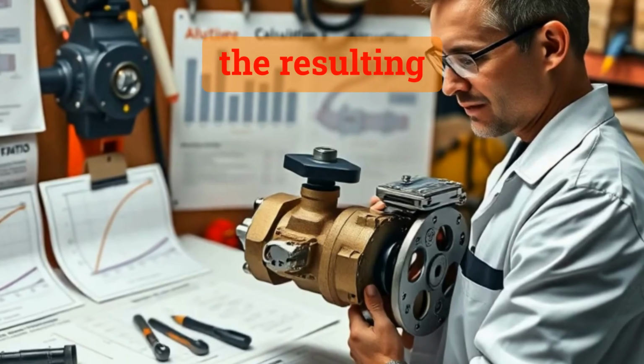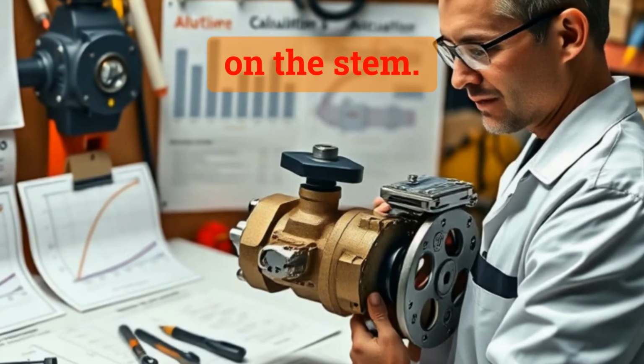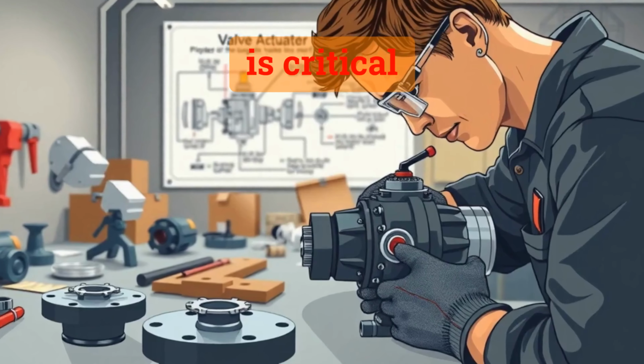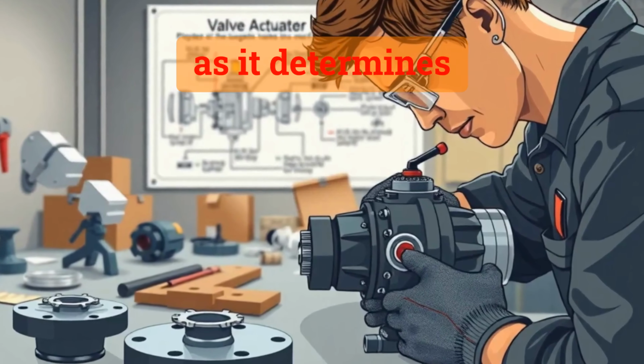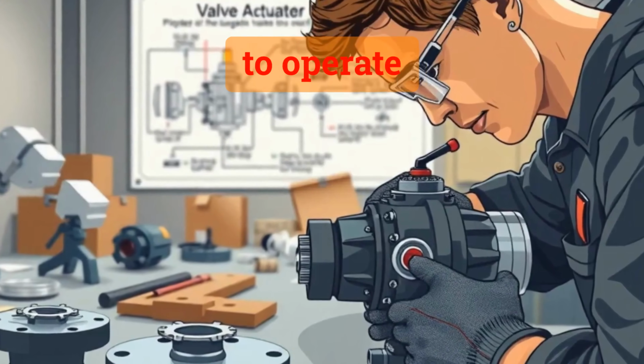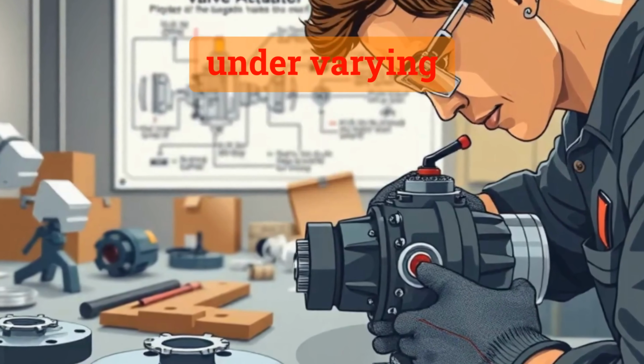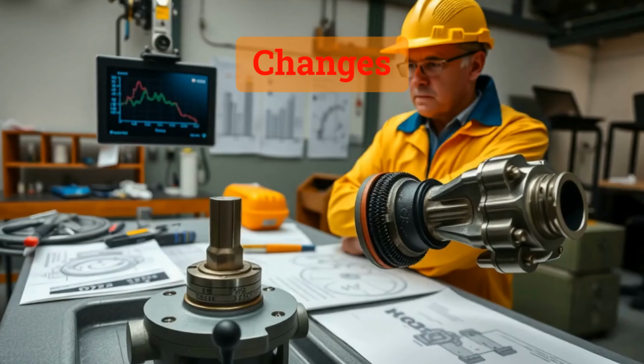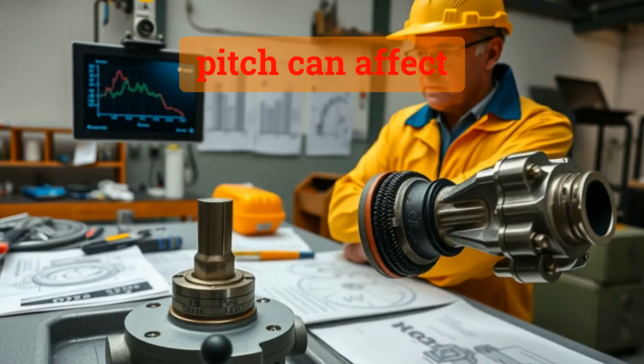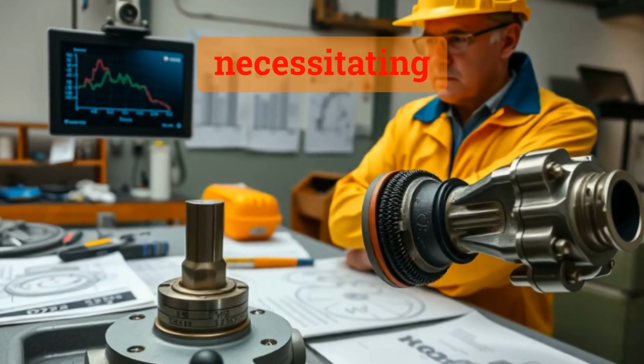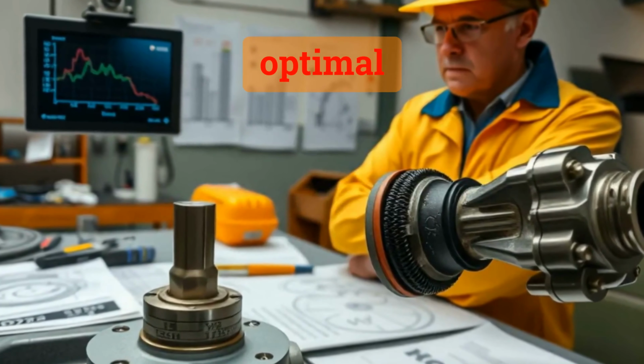actuator with the resulting axial force, or thrust, on the stem. This ratio is critical when sizing actuators, as it determines the mechanical advantage needed to operate the valve reliably under varying conditions. Changes in stem design or thread pitch can affect this ratio, necessitating recalculations to maintain optimal performance.